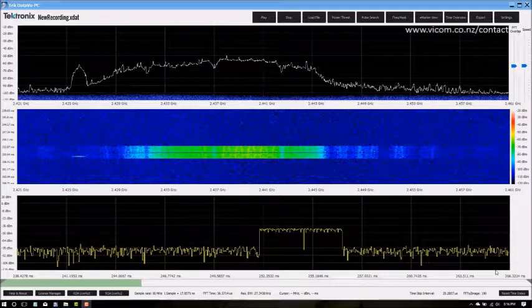In this video, we'll demonstrate some of the combined capabilities of DataVu-PC and the RSA, as well as even dual RSAs. Today we have an RSA 500 series analyzer and an RSA 306. Let's begin by attaching the 500 series to the laptop using the USB cable. We've already attached power and the antenna as well as the trigger.